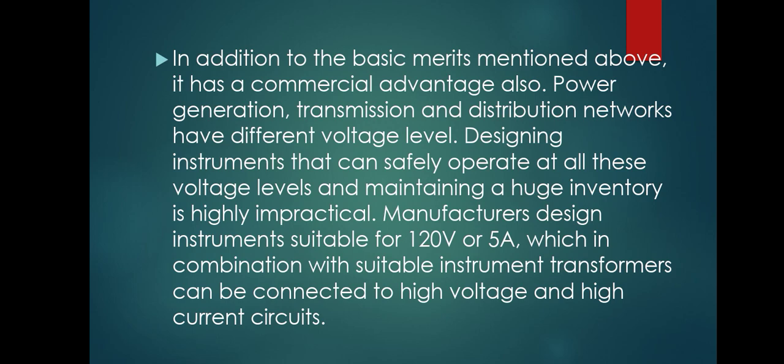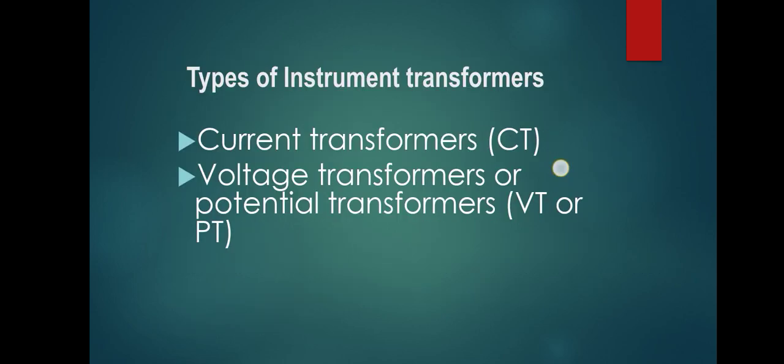Manufacturers design instruments suitable for 120 volts or 5 amperes, which in combination with a suitable instrument transformer can be connected to high voltage and high current circuits.